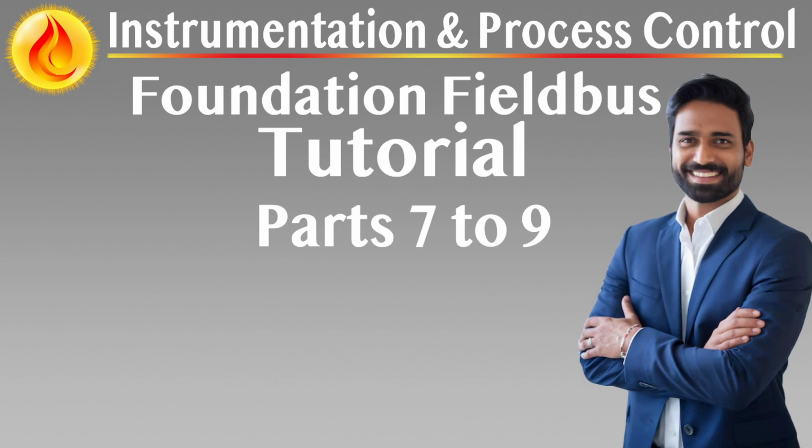Tag and address assignment occurs during commissioning or when a new device joins the network. Devices initially operate in a temporary address space, typically 0xF8 to 0xFB, and are discovered using a probe node PN and probe response PR exchange. System management services then assign permanent node addresses and PD tags based on system configuration. The assignment protocol ensures that device replacement can occur without disrupting existing configuration, provided that the new device has matching credentials and function block structures.